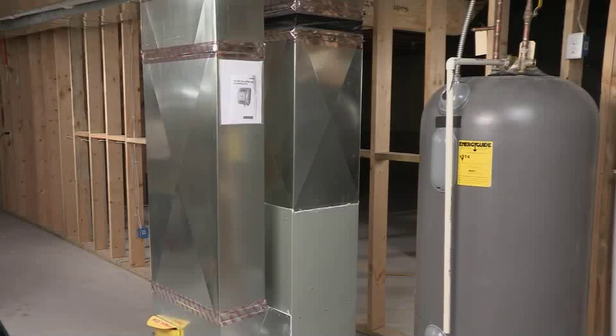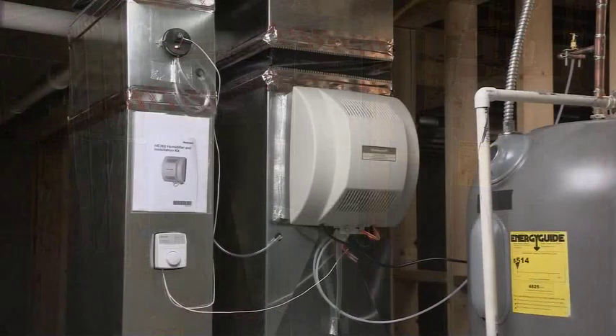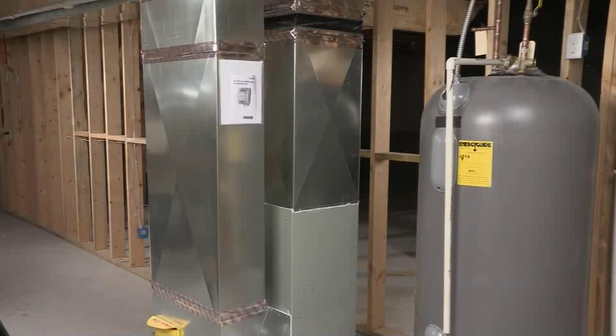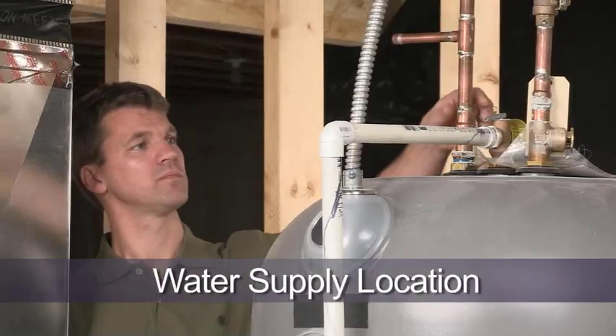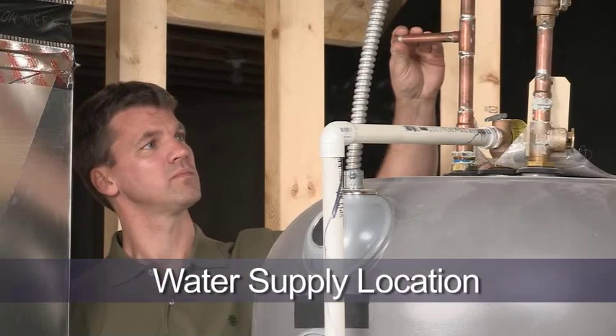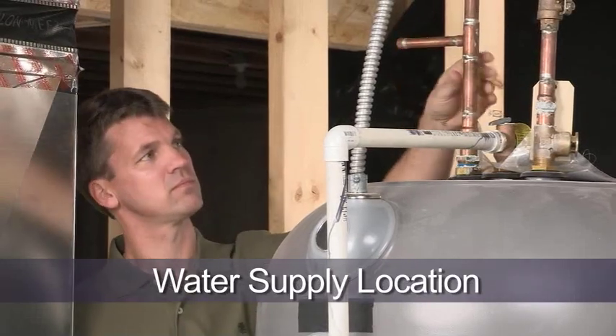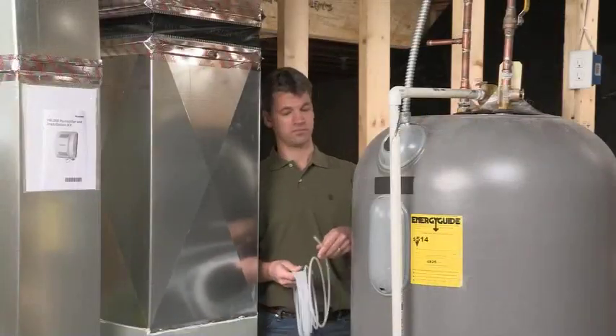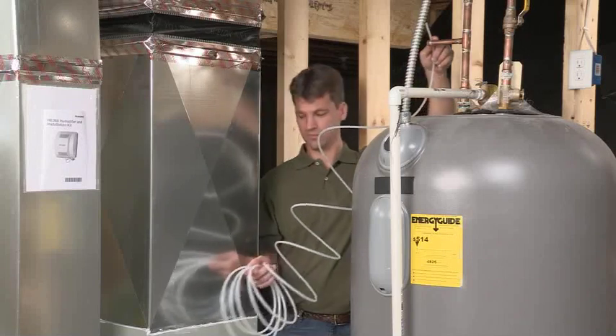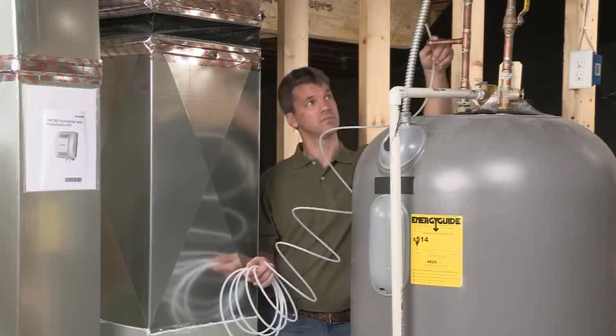Most importantly, choose a location where there is enough room for the unit and where you'll have easy access for routine maintenance. Do not install the humidifier on the furnace itself. In this video, we'll be installing the humidifier on an updraft style furnace. If you have a different style of furnace, refer to the written instructions for help on where to install your humidifier. You'll also need to confirm the location of your water supply. You can use hot or cold water, hard or soft water. Just make sure the feed water tubing that's provided is long enough to connect the water supply with the humidifier's solenoid valve.